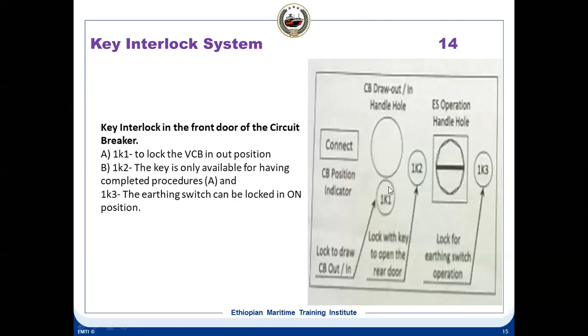So you rack out the breaker from here, take this key, put the key here. When you turn the key, you can enable this earthing switch to be made. And when the earthing switch is made, you take out this key. So this key is with you in your custody. Unless you put this key here, you cannot make the earthing switch back to normal. So once you finish your work, you can put the key here, make the earthing switch off, then put the key here. So that this key can be removed. Once you remove this key, then you can put the breaker back. So it goes in like that in sequence. So this is the key interlock systems.